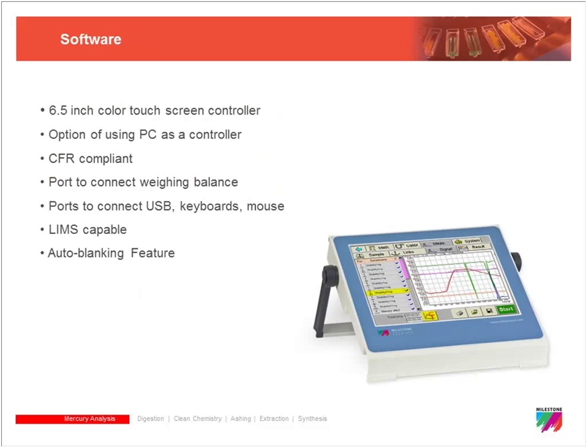The system is controlled from either the color touchscreen terminal located in the picture here, or it can be completely controlled from a laptop PC. Both would run on the same software. It's fully CFR compliant and allows for multiple user access levels. It also records any logins or changes made to the system as part of that CFR compliance. It has several USB ports allowing you to connect keyboards or mice to make it a little more user-friendly, and it will also connect to some of the more common balances to allow for your mass inputs to be done as easily as possible.